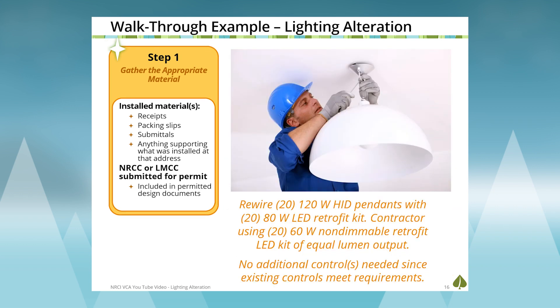Let's start with step one by gathering the appropriate material. Our example project is rewiring 20 120-watt HID pendants within an existing conditioned warehouse and replacing them with 80-watt LED retrofit kits. The contractor found an approved alternative — a 60-watt non-dimmable LED retrofit kit. We'll use the Virtual Compliance Assistant to determine if this alternative is equal or better. We won't need to worry much about controls, as the existing controls meet the minimum requirements of the 2022 code cycle.